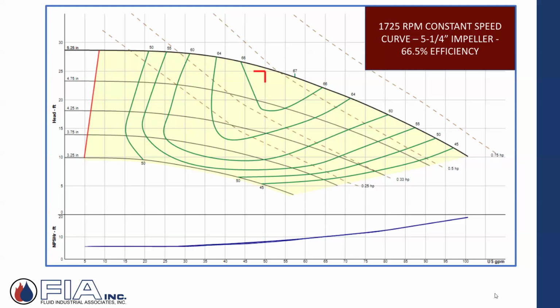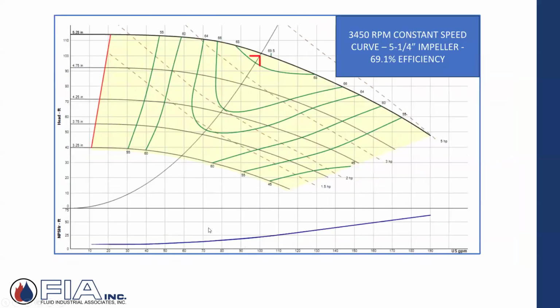So kind of continuing on with our moving into variable speed pumping. They're just showing a quick example here of a pump curve. It's constant speed. And what we're showing here is the design conditions that we talked about in our example of that 100 gallons a minute, which is reflected down here on the horizontal curve, and the 100 feet of head, which again, kind of unusual, but we pick a pump, got a 3450 RPM constant speed motor, and the curve with a 5 1/4 inch impeller.